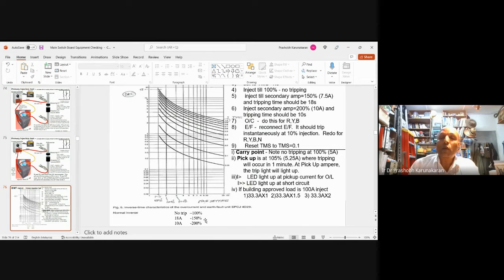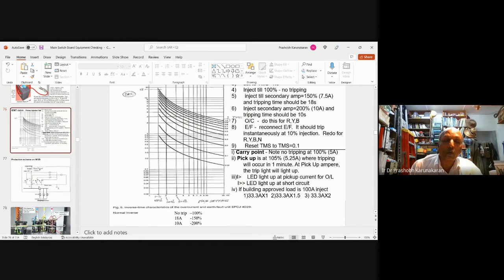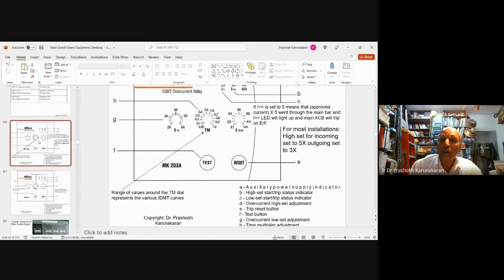You inject 150%, it must be 18 seconds according to this graph. It's 18 because different OC got different graph. According to this graph is 18 seconds. And then 200%, which is 10 amps, according to this graph, it is 10 seconds. So to do the test, you must tune this one to 1. You see this TM here, you must tune to 1. And then do the test.